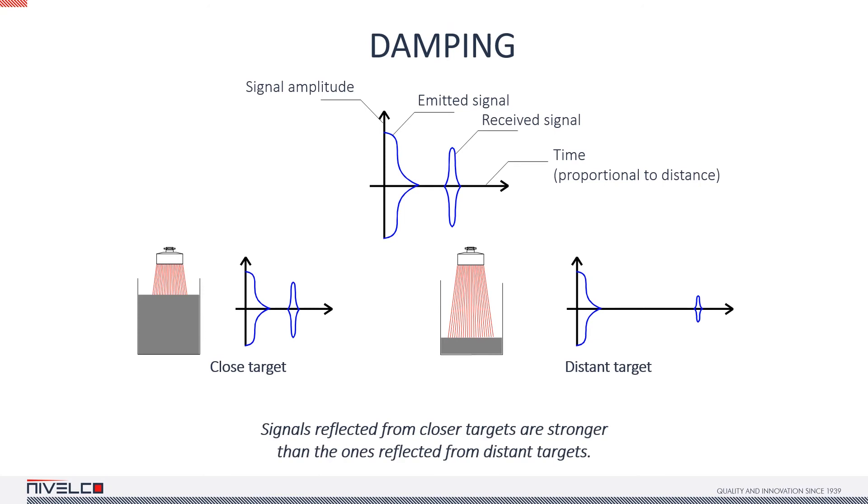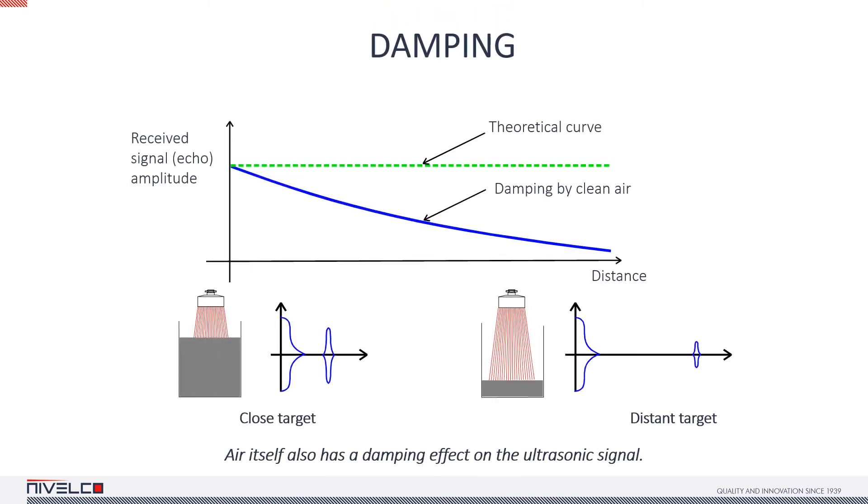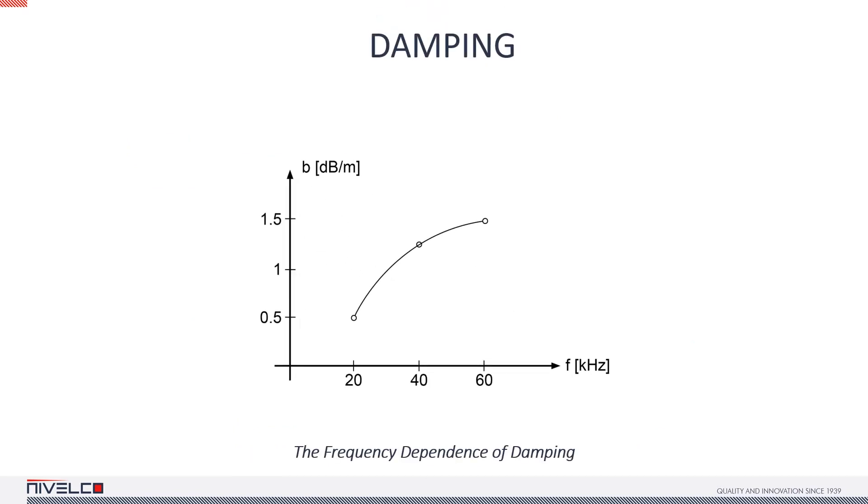While the target is close to the device, it provides a clear echo, but as the target gets further away, the echo diminishes, and after a while it gets so weak that the sensor is unable to pick it up. The green dotted line is the theoretical curve indicating the signal level when there is no damping at all. As soon as a damping factor like air or other gas is introduced, we get a curve like the blue one. The longer the signal has to travel, the weaker the echo gets. Damping depends on various factors like the physical properties of the atmosphere above the medium or the frequency of the device.